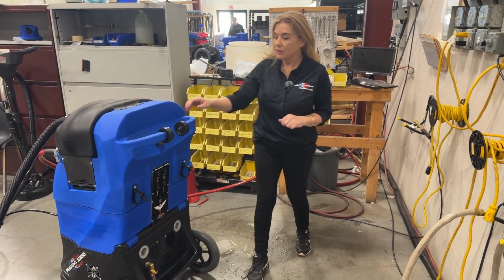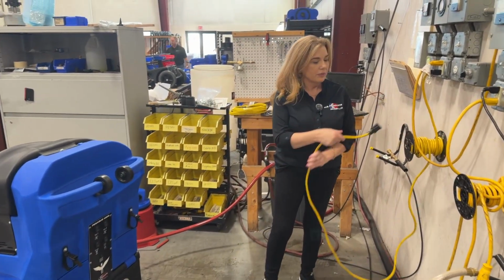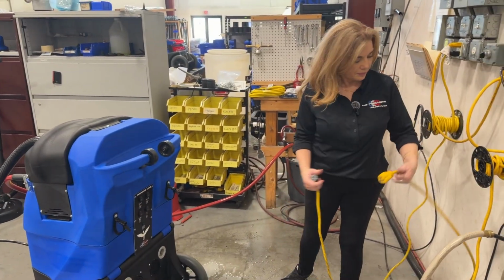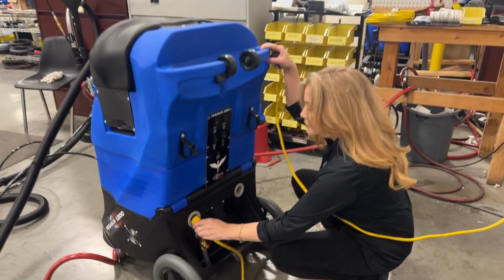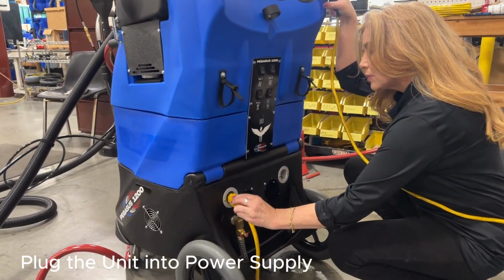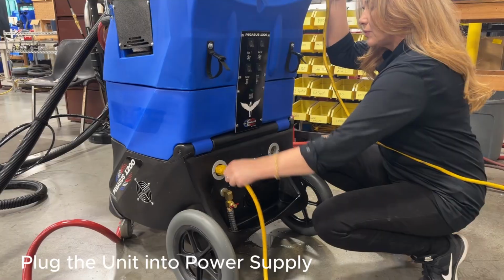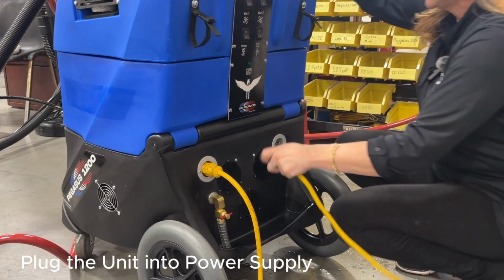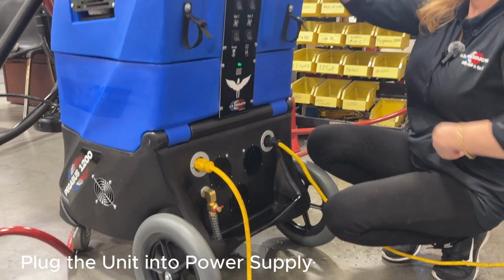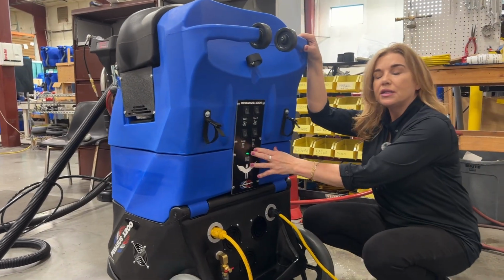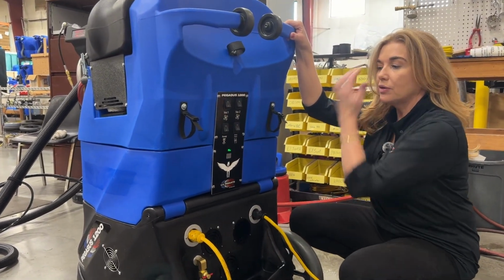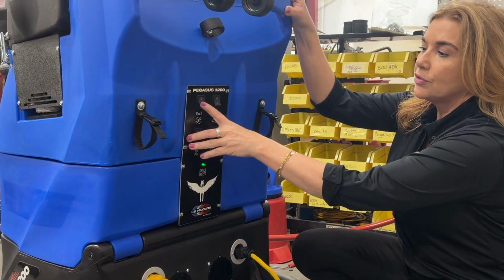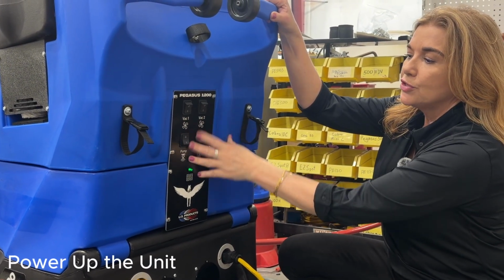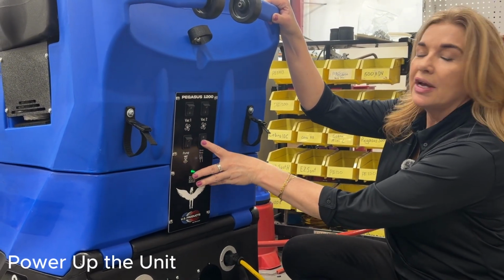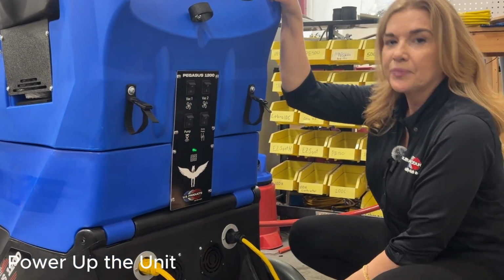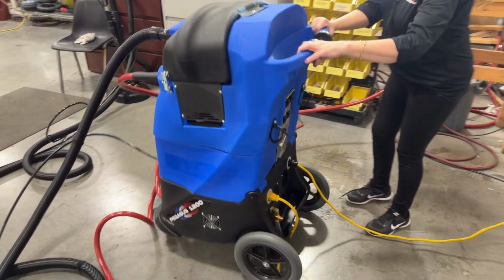Now we're going to plug the unit in for power supply. We've got our 2 cords here—cord 1 and cord 2. You'll see the green light illuminated, which tells you that you're on 2 separate breakers and the machine is ready to go. We'll turn on vacuum 1, vacuum 2, your pump, and your dump pump. Now the machine is ready.